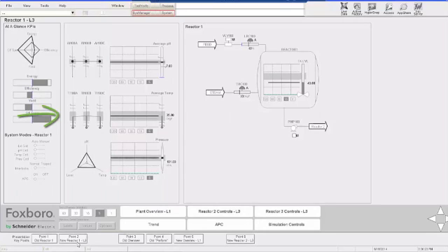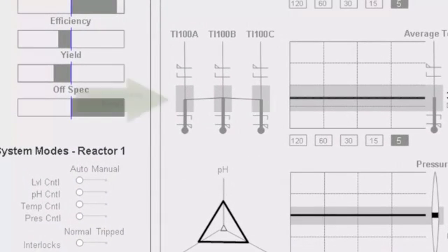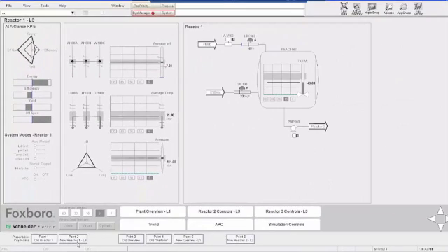We can see right away that all three of these values are falling within the optimal operational range, just at a glance. I don't need to do a mental calculation, and I don't need to look around for the three different digital values. This helps prevent human error, because a drifting value becomes much more obvious within the context of an analog bar.